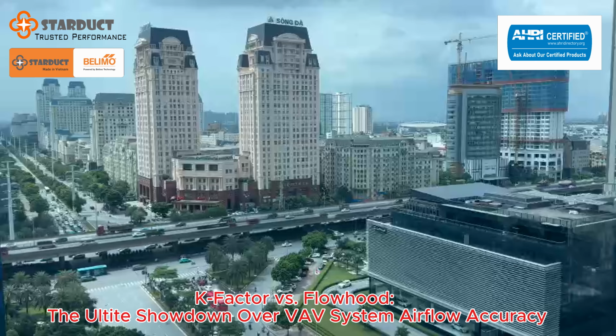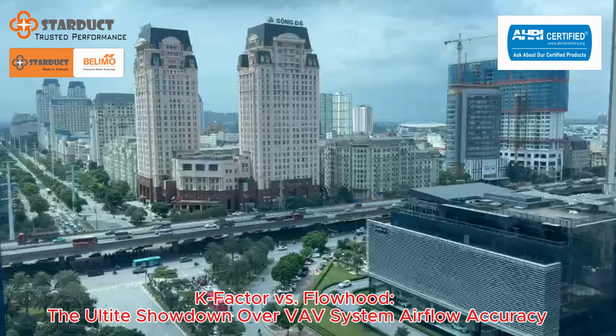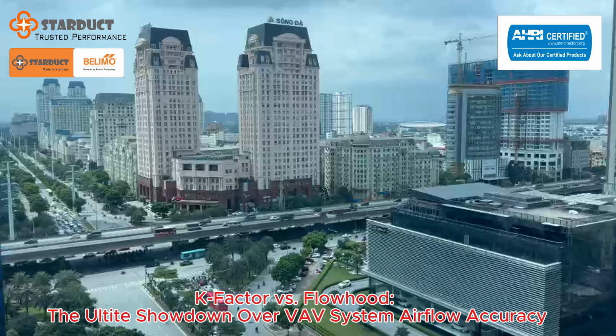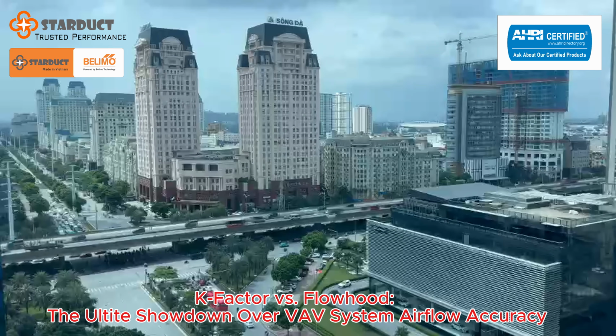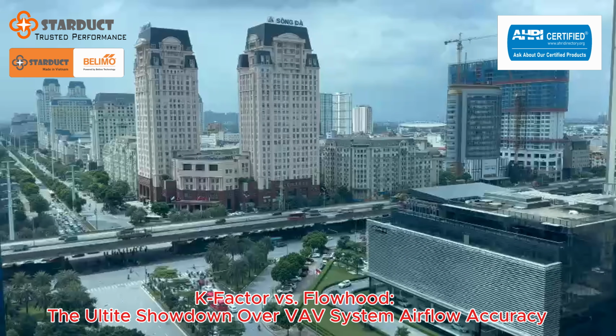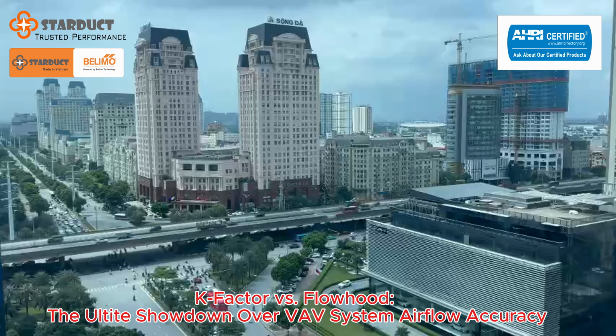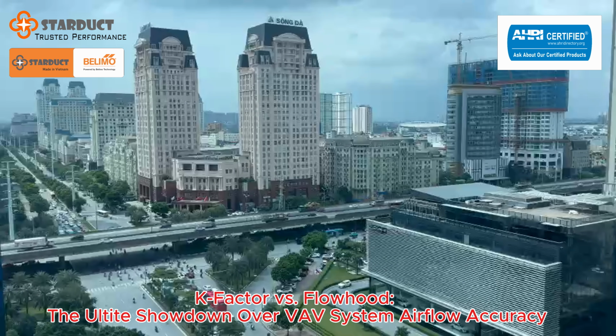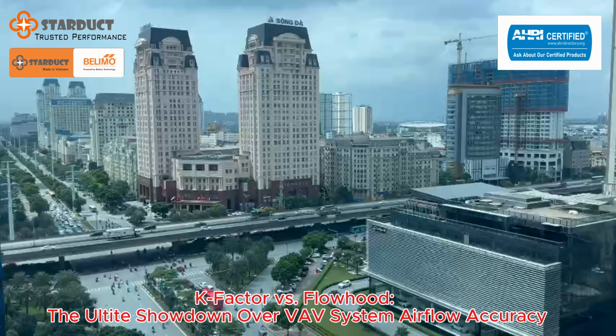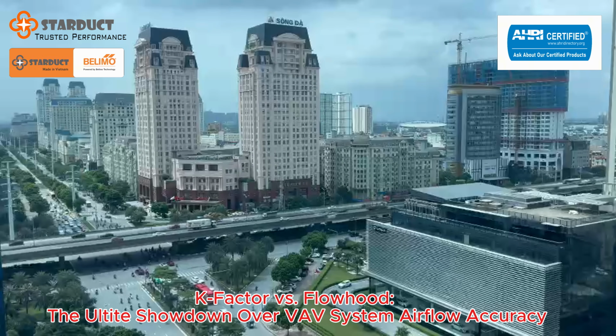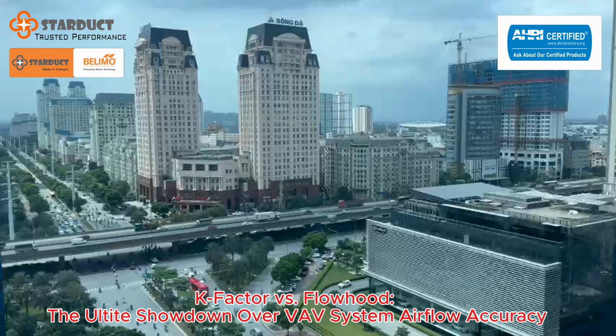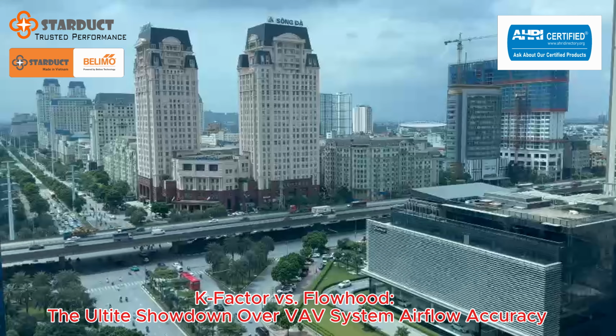Exactly. Which brings us right to the core tension, the central question for today. When we're commissioning these VAV systems, should our primary trust, our main reliance for getting that airflow right, be placed on the factory-certified theoretical constant, the K factor? Or should we be insisting on the mandatory hands-on process of field calibration using physical tools?